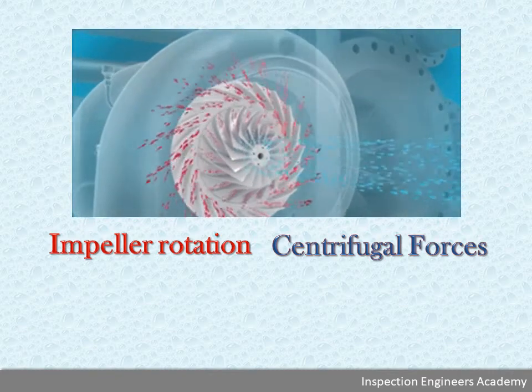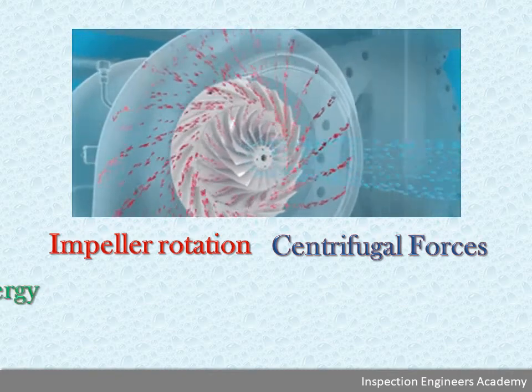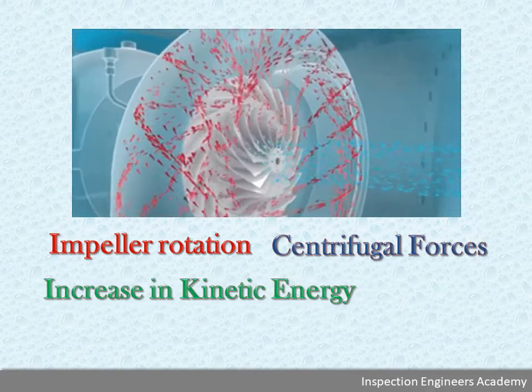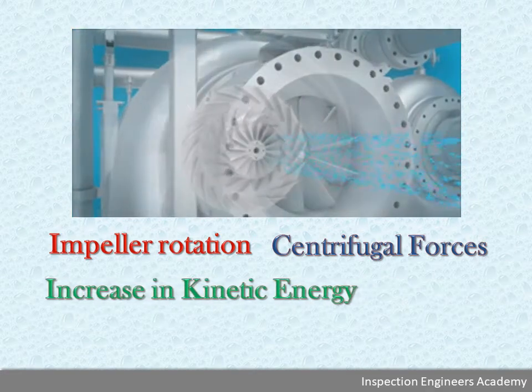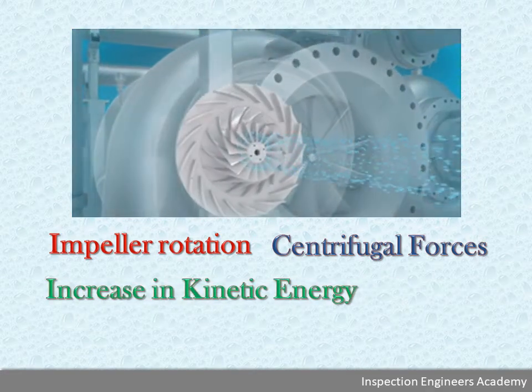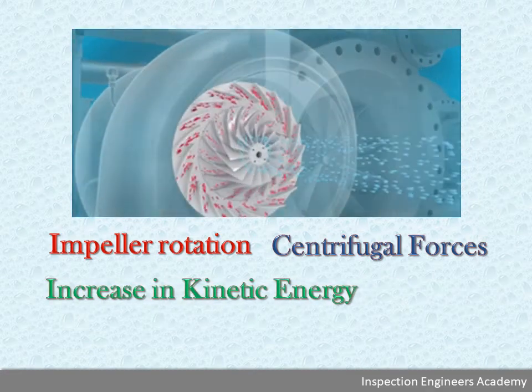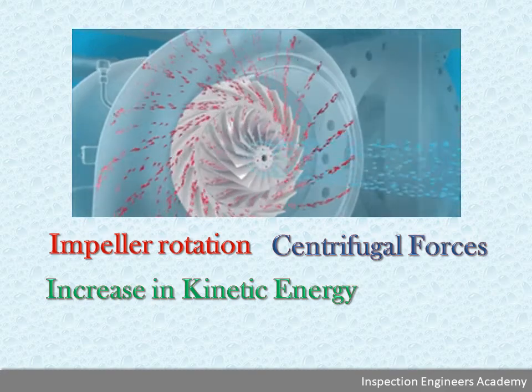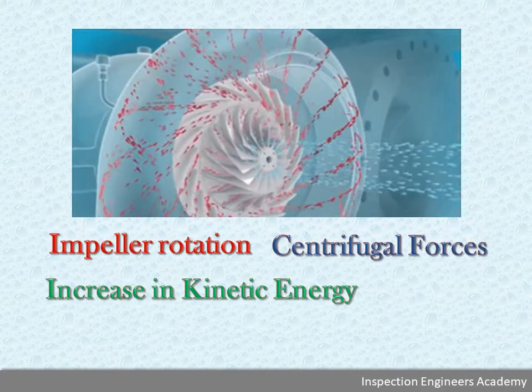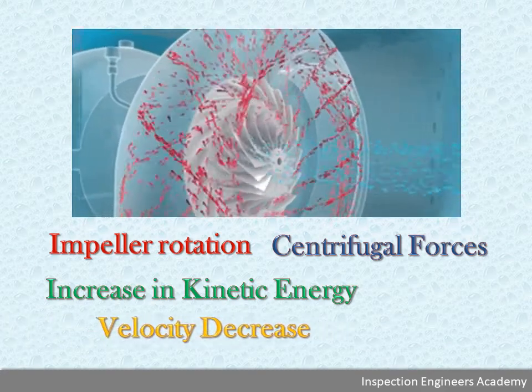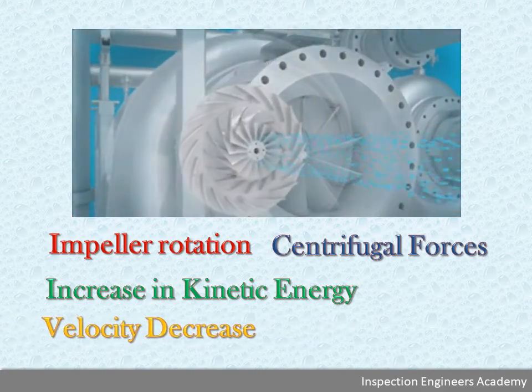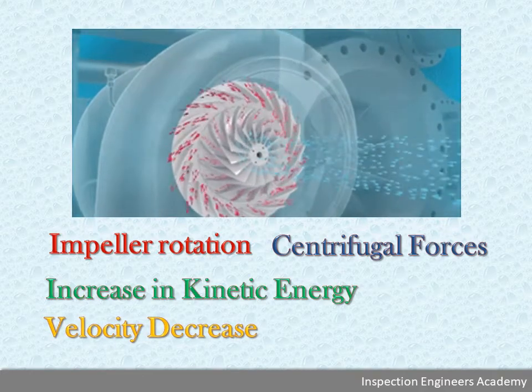Gas passed between the radial vanes of the impeller in the radial direction, causing an increase in gas kinetic energy. On the way out through the diffuser, gas velocity is decreased and kinetic energy is converted to an increase in gas pressure.